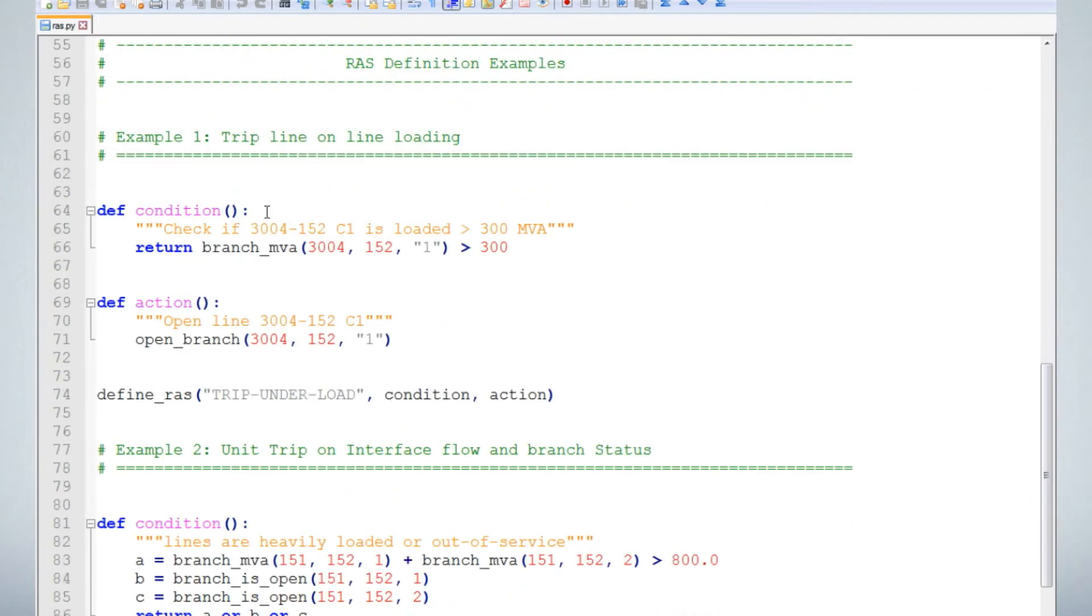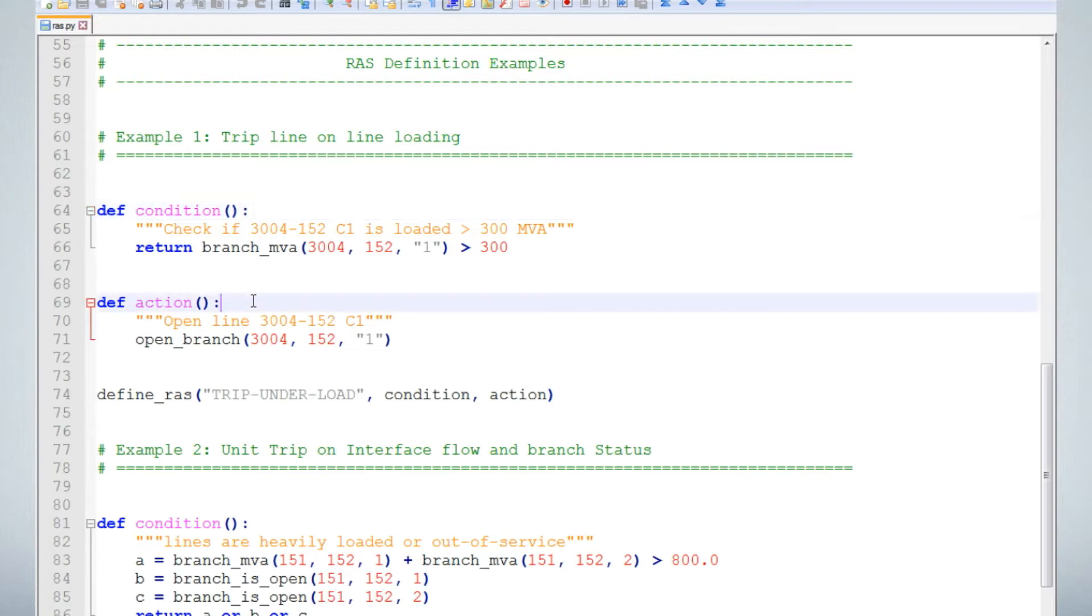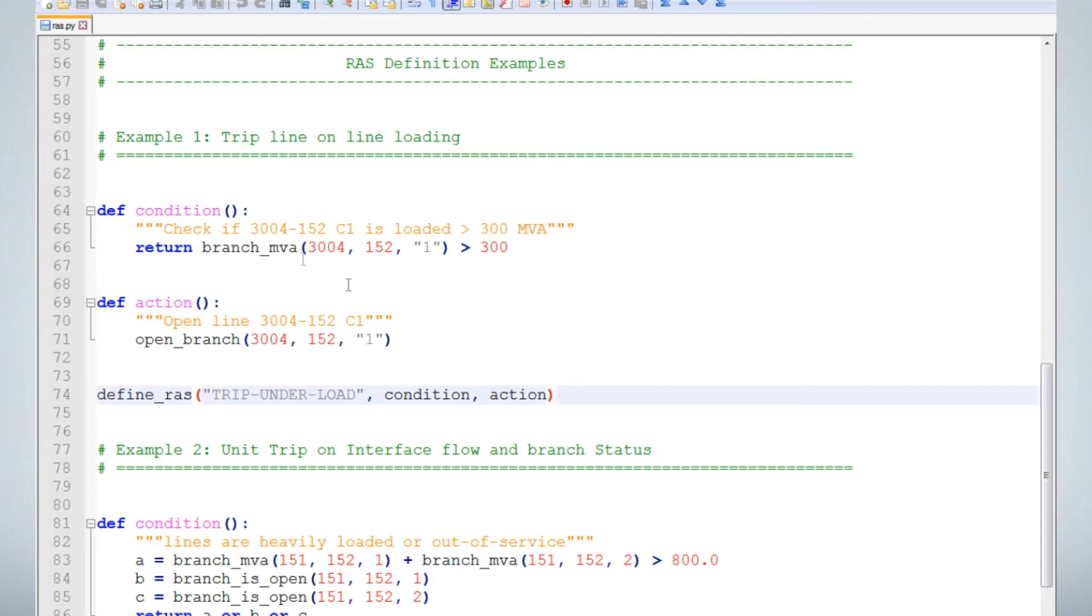A scheme definition has three parts: a condition function that defines the conditions that must be met, an action function that defines the action for when the condition is met, and a define RAS statement to link the two functions together and give the scheme a name.